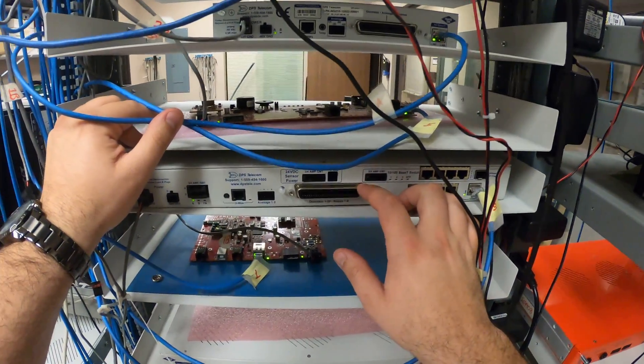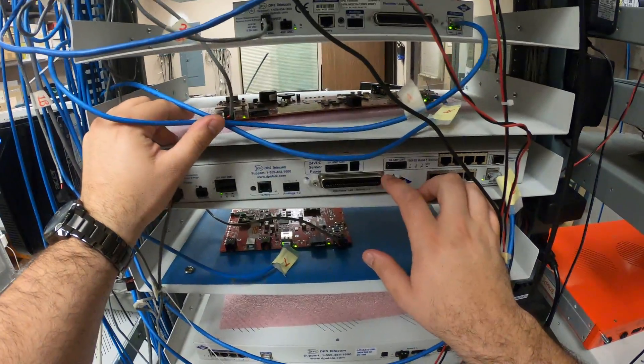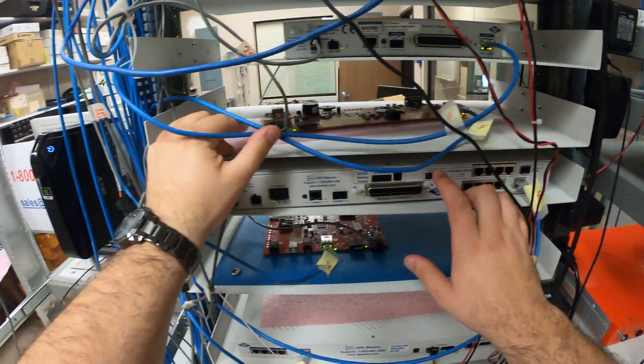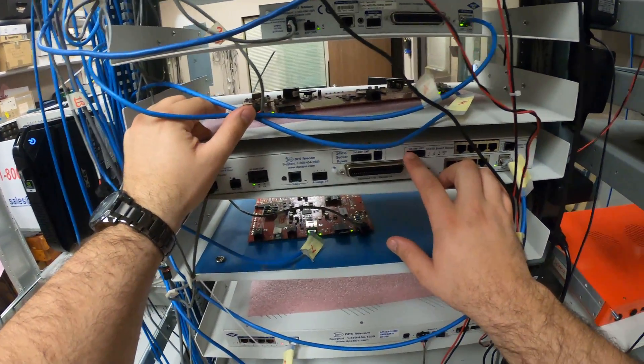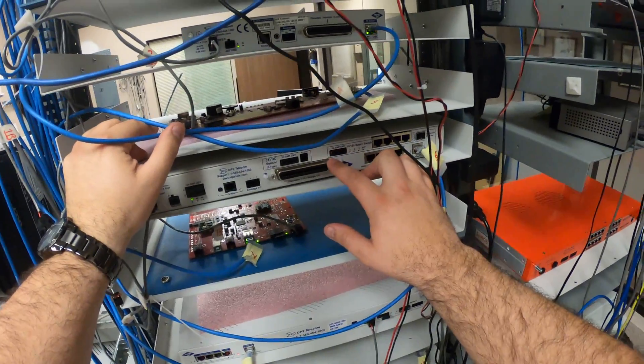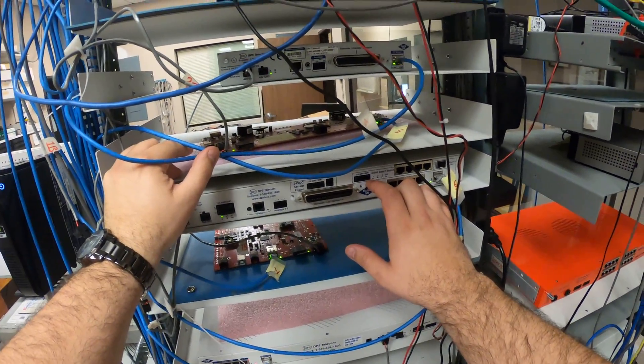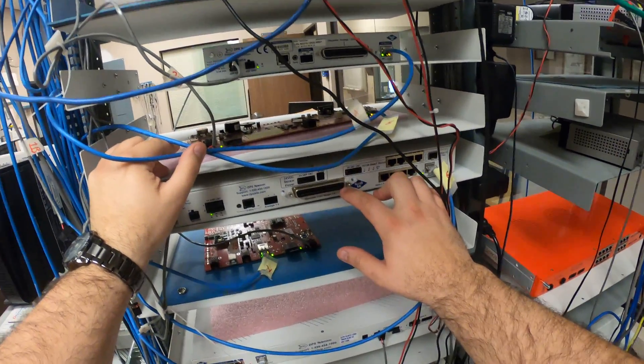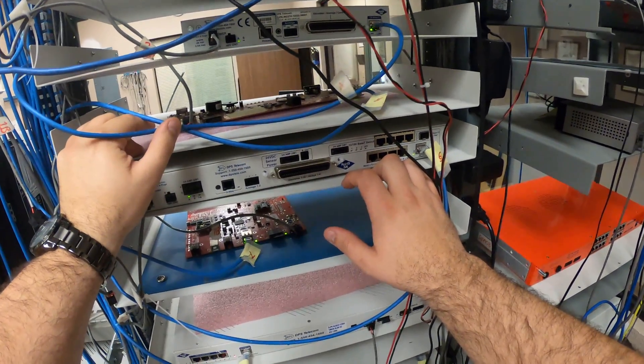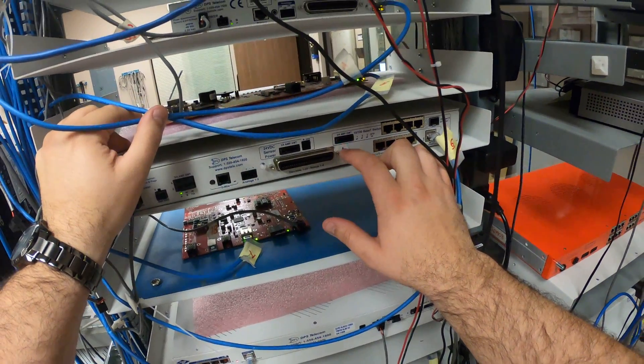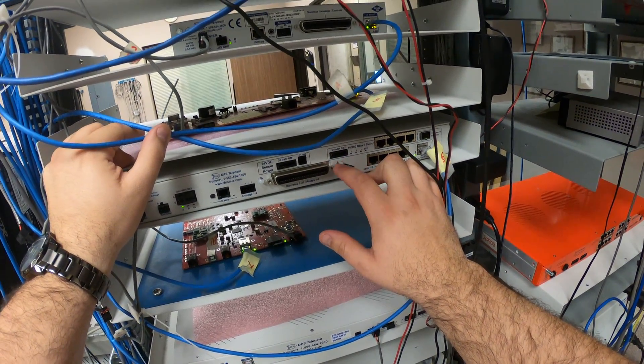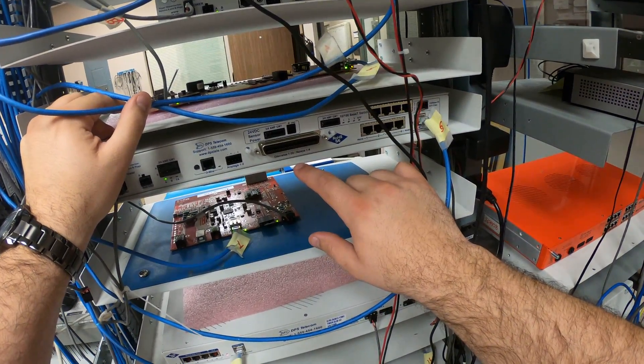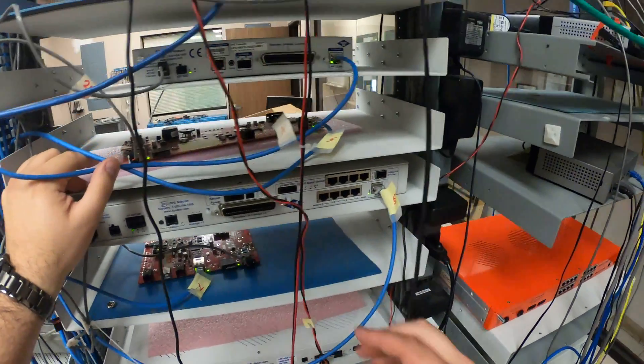And then the 50-pin Amphenol. I hear a lot of questions about this. Some people aren't sure how to terminate. This commonly will go to a 66 block or a wire wrap panel. We have a pluggable backplane. You can also just go to bare wire if you want to splice in the pairs yourself. So this is a handy way to terminate a lot of different inputs and outputs. In this case, it's 20 discrete inputs and four control relays.